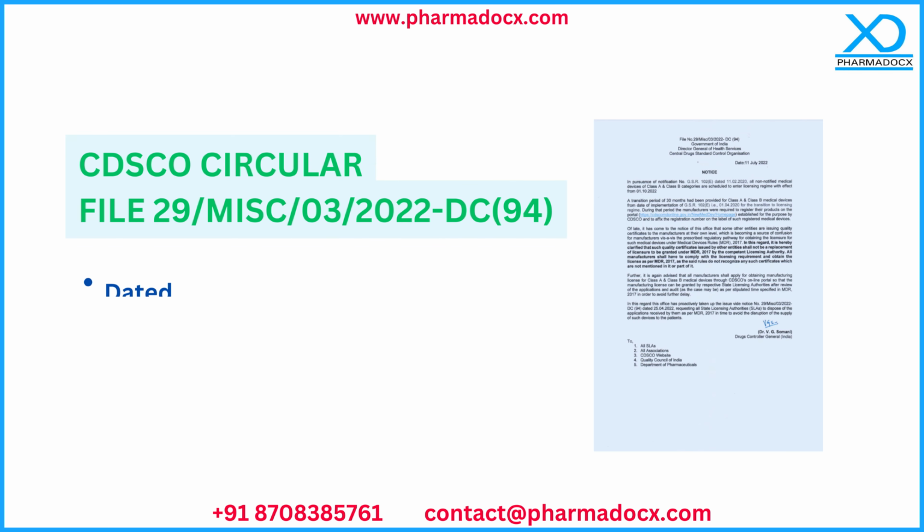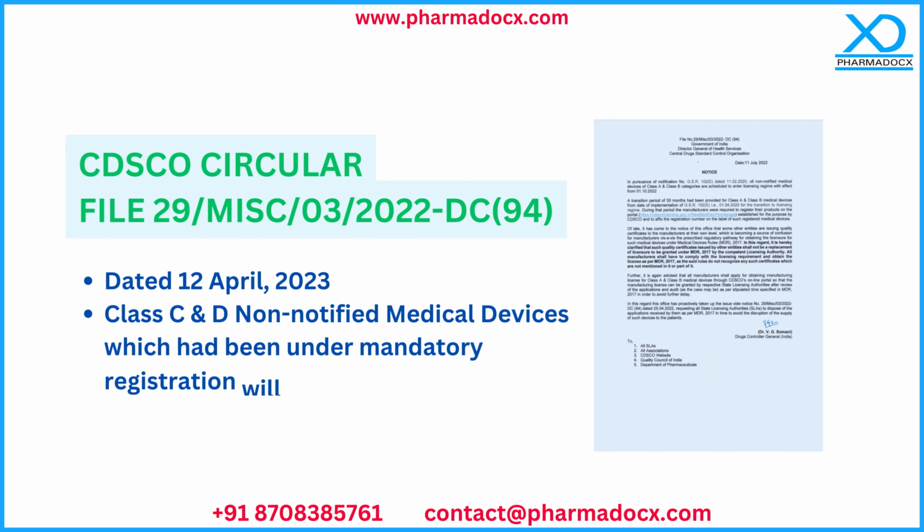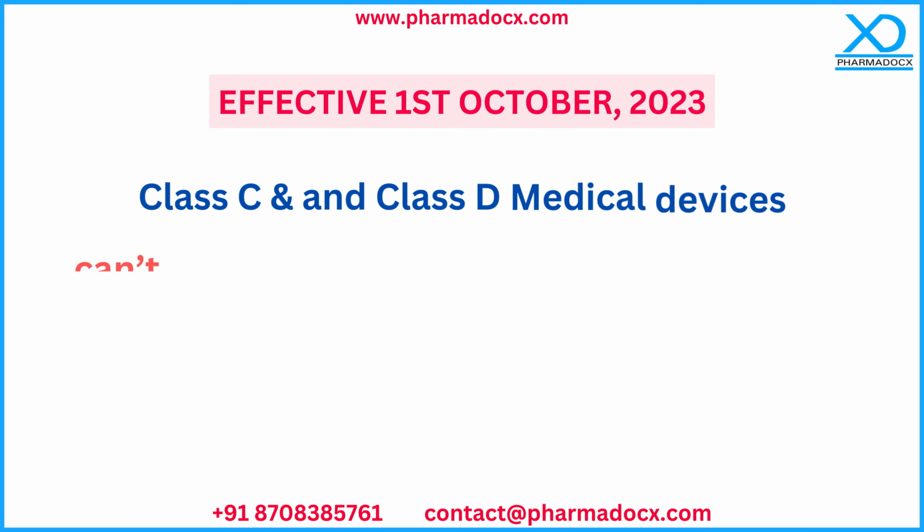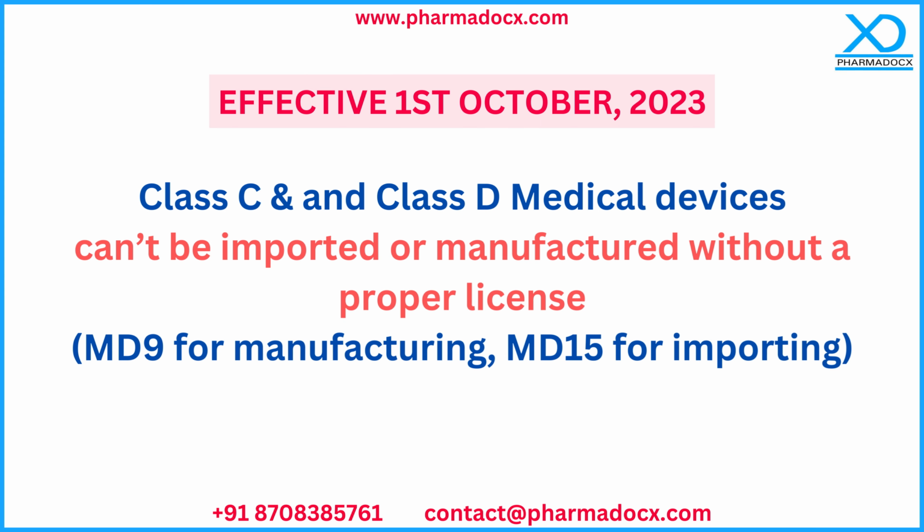CDSCO had further released a circular vide file number 29/MISC/03/2022-DC-94 dated 12th April 2023, in which they had informed that the Class C and Class D non-notified medical devices which had been under the mandatory registration will come under the licensing regime with effect from 1st of October 2023. That means with effect from today, which is 1st October 2023, no Class C and Class D medical devices can be manufactured in India or imported into India without having a valid license on Form MD9 for manufacturing and on Form MD15 for importing.